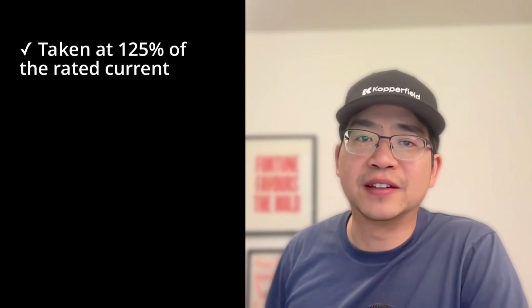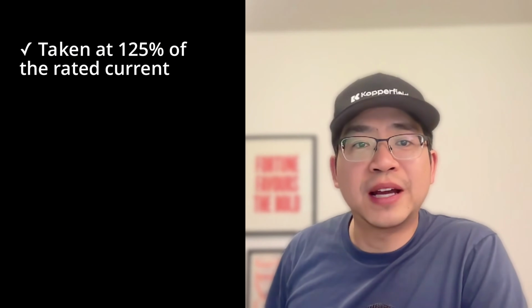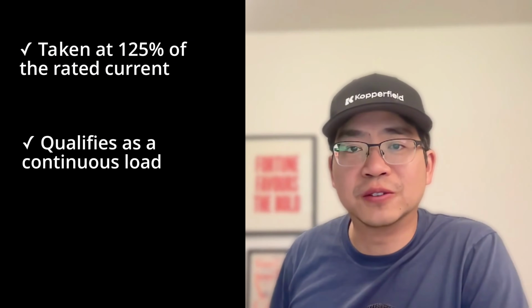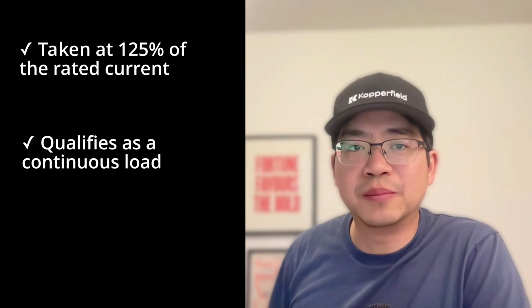Secondly, we've heard that most AHJs want to see the EV chargers taken at 125% of the rated current because it runs for more than 3 hours continuously and it qualifies as a continuous load under Article 100. And this is what most electricians are choosing to do on their calcs. Finally, if your AHJ is enforcing the 2023 NEC, Article 220.57 specifies that EVSE load shall be calculated at a minimum of 7,200 VA for each EV charger, or 100% of its nameplate rating, whichever is larger. That's a change from how some folks are used to doing it. If you're not sure how your local AHJ wants it handled, it's always a good idea to double check before submitting. Now let's get into the load calculation.